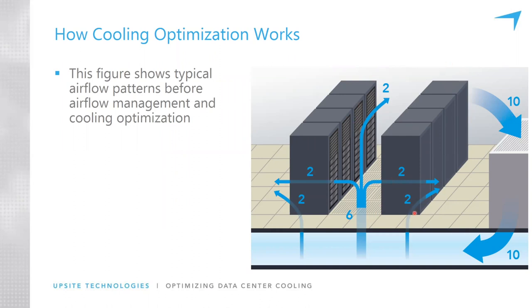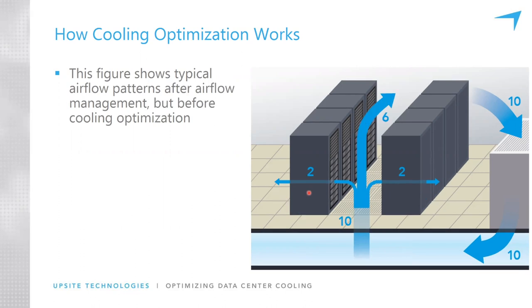So obviously we want to seal these bypass openings, right? We want to block this bypass airflow. Absolutely. And do you think that if we seal these openings and block these 2 units and these 2 units of air, will that affect how much bypass airflow is in the room? It's a trick question, kind of. The answer is, well, yes, it limits the amount of bypass airflow coming out of the raised floor underneath cabinets, but it doesn't change the amount of bypass airflow in the room.